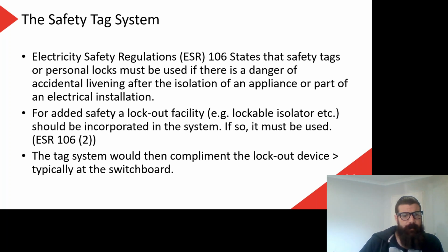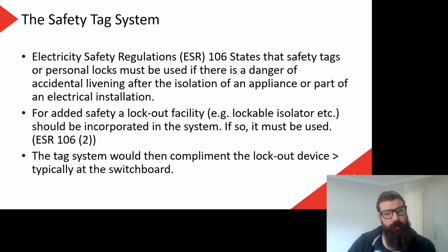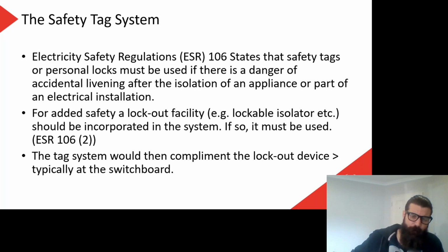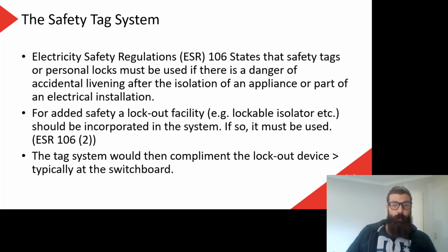The safety tag system. The electricity safety regulations 106 states that safety tags or personal locks must be used if there is a danger of accidental livening after the isolation of an appliance or part of an electrical installation. So that means in the law it says that we must lock and tag our isolations once we've done them.